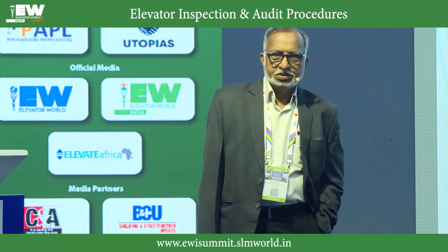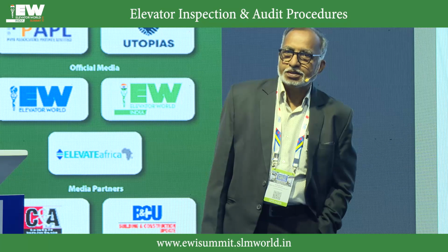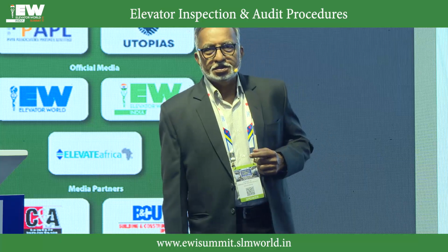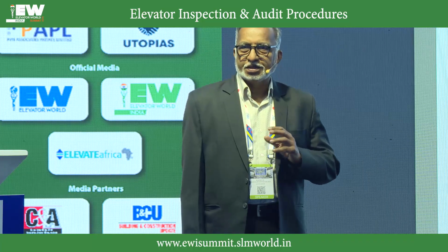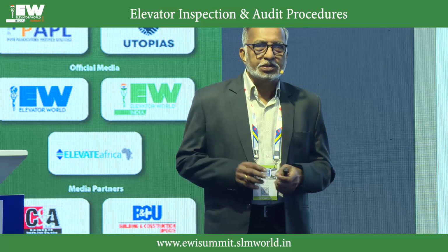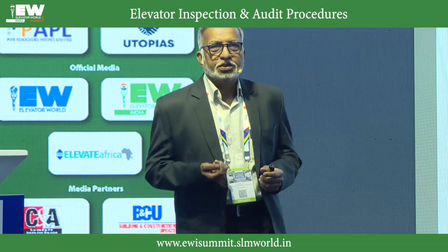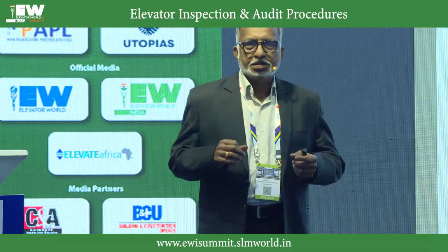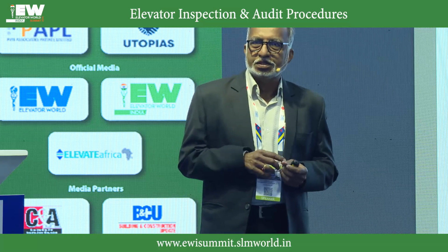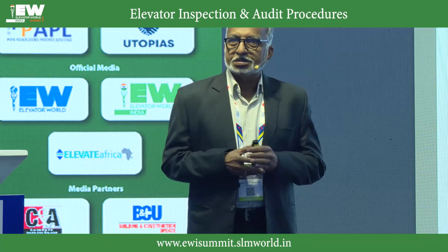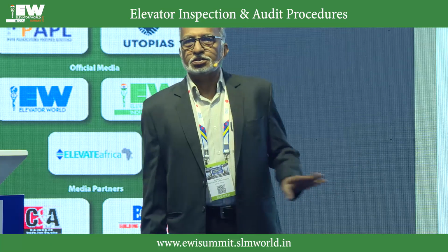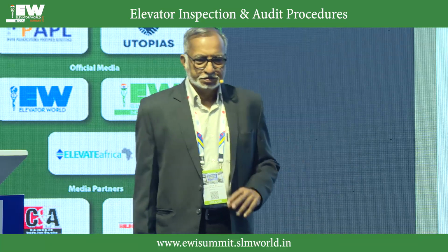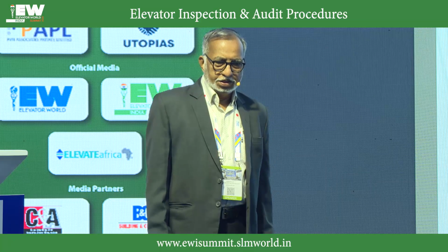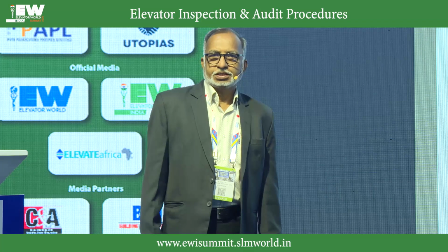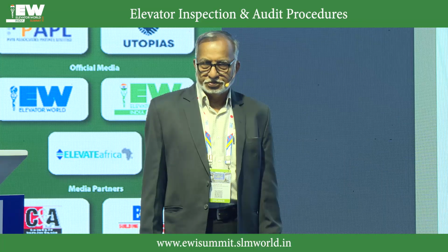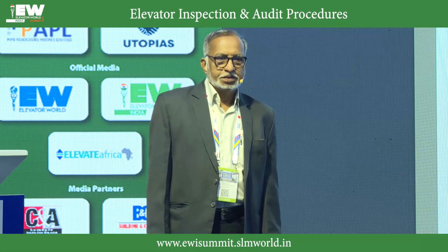De-locking system - it's everywhere in the door, but sometimes the door locking key and the de-locking arrangement on the panel don't engage properly, so even after putting the key inside the door hole you are not able to open the door. This creates a problem during emergencies. So you have to ensure all door locking is proper and check it on all floors, not just a sample test - a full test. Door earthing, door header, door seal, de-locking, and shaft lighting all need to be checked so you can work freely in the elevator shaft.